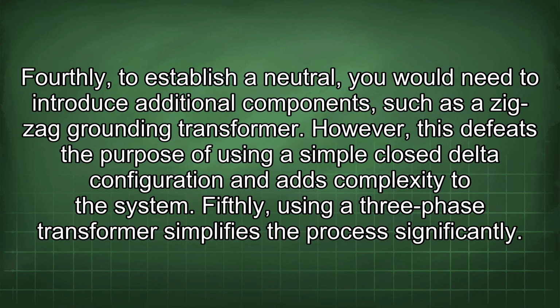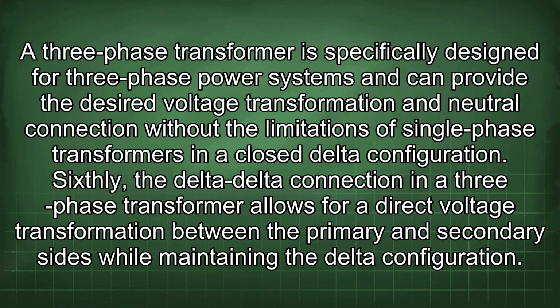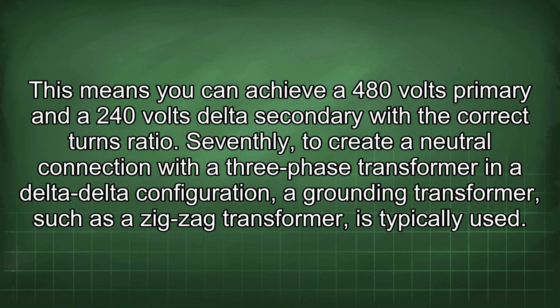Fifthly, using a three-phase transformer simplifies the process significantly. A three-phase transformer is specifically designed for three-phase power systems and can provide the desired voltage transformation and neutral connection without the limitations of single-phase transformers in a closed delta configuration. Sixthly, the delta-delta connection in a three-phase transformer allows for a direct voltage transformation between the primary and secondary sides while maintaining the delta configuration. This means you can achieve a 480 volts primary and a 240 volts delta secondary with the correct turns ratio.